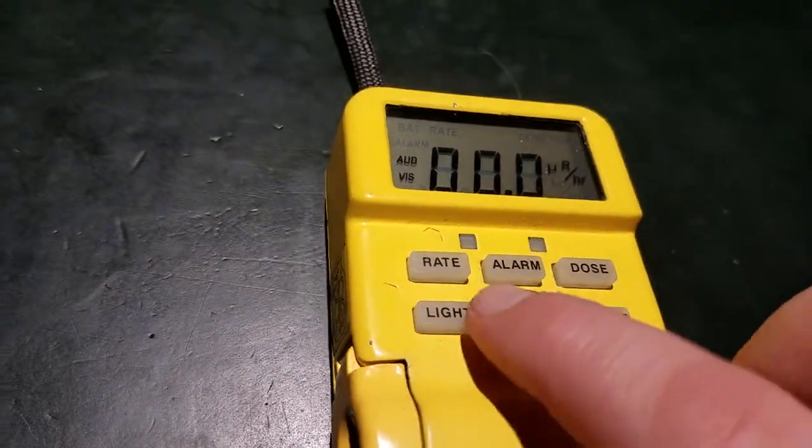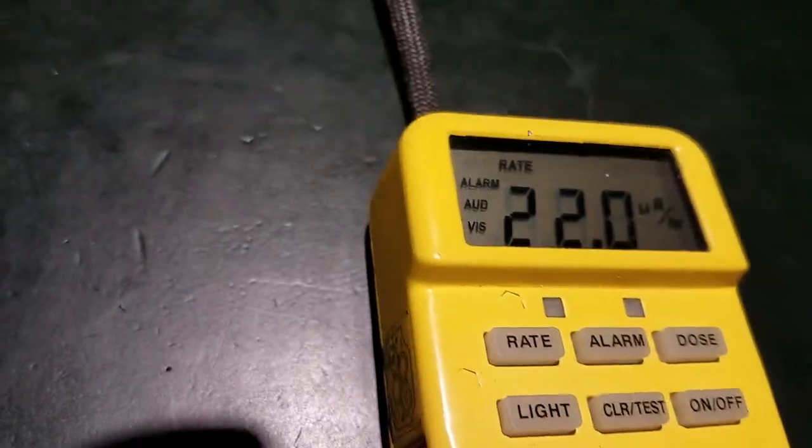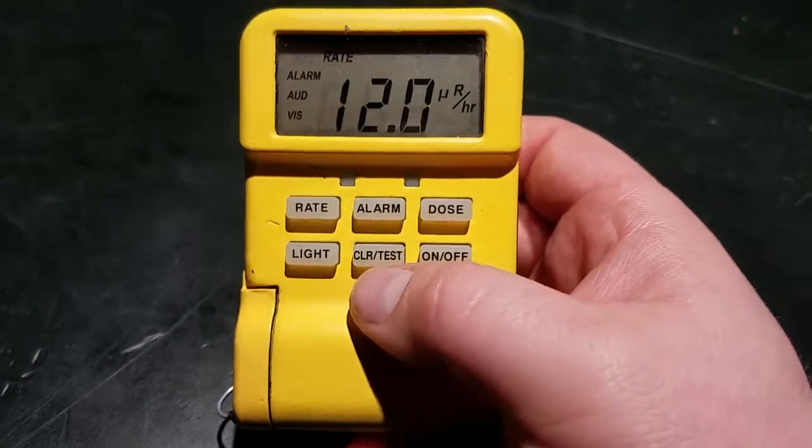You see that the light here on the left is flashing. Now that I've cleared it from that higher radiation field, I hit clear and it'll stop. The alarms are latching, so you have to hit clear to get them to stop once you've cleared the radiation field.